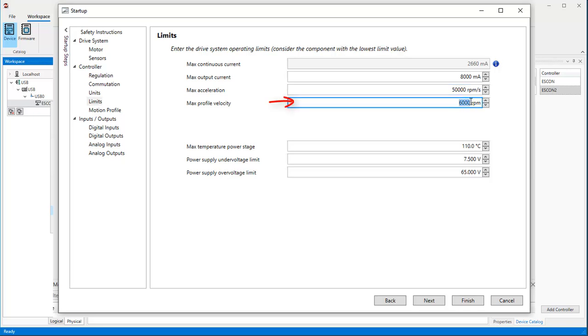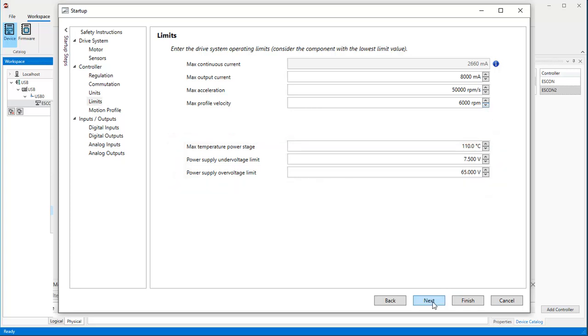Here you can define generally applicable limits. For instance, I want to limit the maximum current for my motor to 3 times nominal or about 8000 mA. Reasonable maximum acceleration values for motors without load lie in the range of 10,000 to 100,000 RPM per second. The factory setting is unreasonably high. I set 50,000 RPM per second as a limit. As you can see, the maximum profile velocity is set to the previously specified value and you cannot enter a higher profile velocity. Usually, there is no need to change temperature and voltage limitations. Press Next.